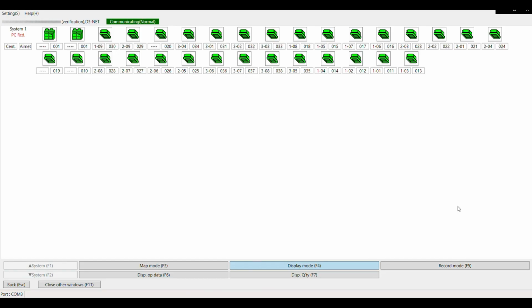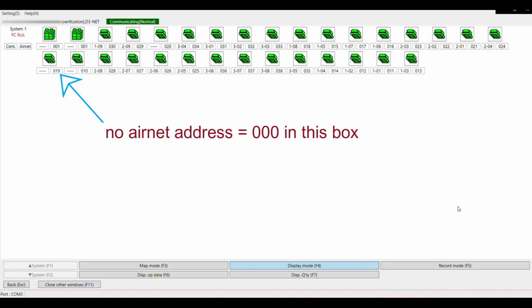If we go back to the network map display and count to I28, the only way we know which unit this particular I28 is, is because of the AirNet address. Take I16 for example. You can see there are just dashes for the group address, and this is because it's part of another indoor icon's group. So if I16 was the unit having issues instead of I28 and we didn't AirNet address this unit earlier on in the startup process, it would just say zero.